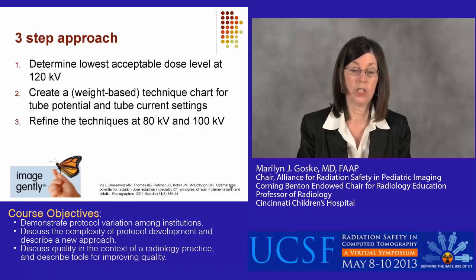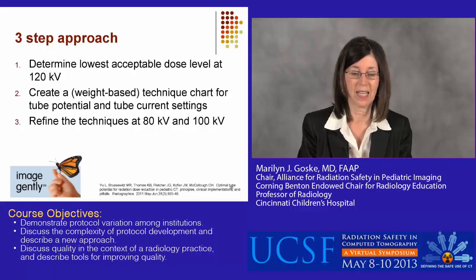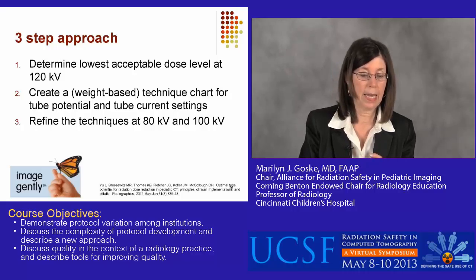that what you would want to do is determine your lowest acceptable dose level using 120 kV. You would then create a weight-based technique chart, or as we advance, maybe a body size technique chart, for tube potential and tube current settings, and then finally refine the techniques again at 80 and 100 kV.